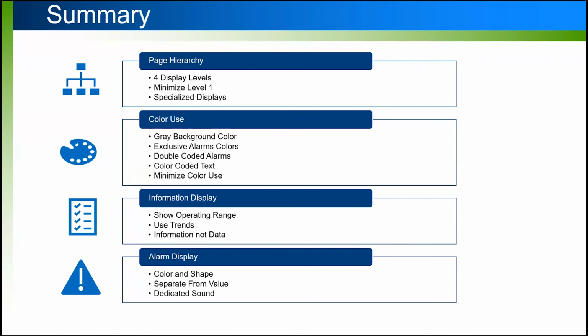And then with alarm display, we're doing the color and the shape. We're separating the alarms from the value. We're not making boxes around the alarm values, we're not changing the process value color, and we're not going to distort the information being displayed to the operator in any way, but we're indicating that there is an alarm associated with that value. And then we just talked about dedicating a sound for every alarm priority to help an operator quickly identify what priority that alarm is.